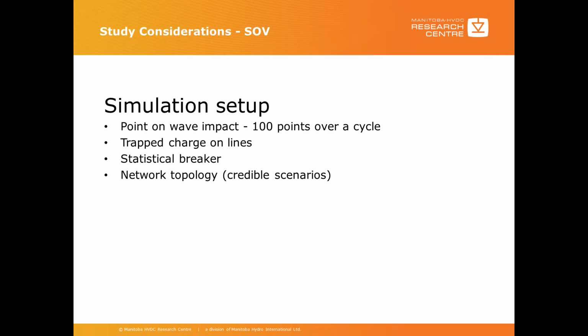The breaker opening and closing time should be selected such that the maximum trap charge is achieved. This will demonstrate the worst-case switching overvoltage. You can also set up various scenarios to capture network worst case, for example, N-1 or N-2.